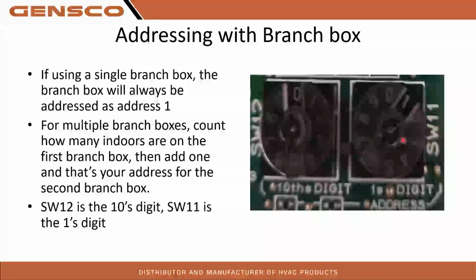Hey, Garrett. Yes, sir. So for those of you listening who have heard the old way of doing that, they used to say, put your outdoor unit at 55 and your branch box at 11, right? It's really hard to screw that one up. But if you were paying attention to the addressing structure for Mitsubishi, right? Your outdoor unit is 50 above the lowest indoor unit. So if you were to make your branch box address 11, that would give your lowest indoor unit address 11. So that would make your outdoor 61.